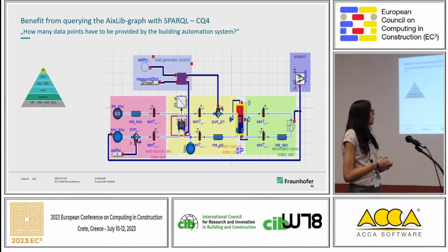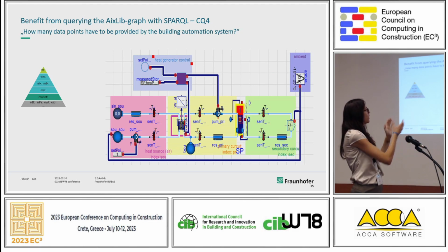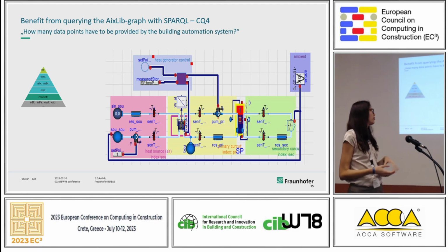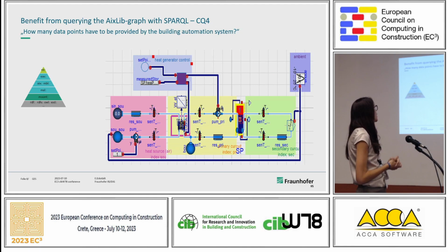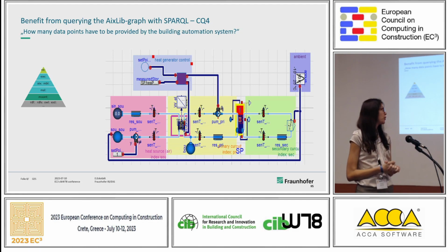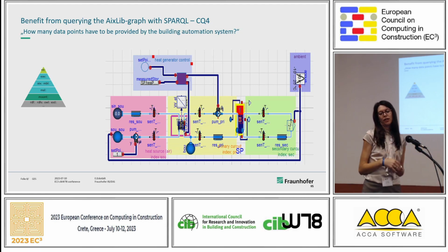So what we see here in general is a heat pump plant. The heat pump is in the purple frame. Then we have a source part. Then we have the primary heating circuit that heats up this storage. And then we have a secondary circuit where a building is served. There's a simplified model for the building heat consumption, and there is a controller, which is in the blue box on top. So if you count, you would see 15 real inputs and outputs, and this is what we expect from the query if everything works out fine.